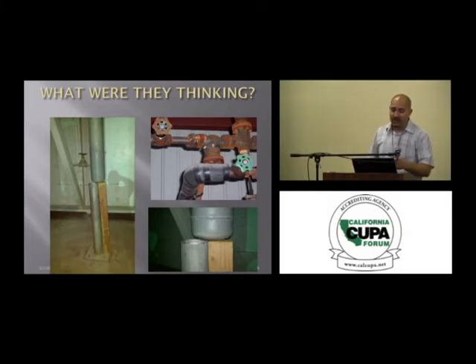And you can see, when we got there, it had been sitting like that for a while, so they thought, before it completely falls off, we're going to shove that 2x4 underneath it to support it. So systems or facilities start to settle down, and things start moving around, and because of the dummy leg being anchored down at the bottom, it had nowhere to go. So what we did, we ended up supporting that pipe temporarily, and then they came back and moved that dummy leg out and then piped it back in, or welded it back in, made it safe.